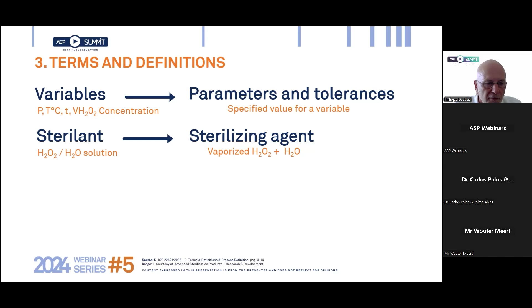Now click again, please. The process challenge device, we'll talk a lot about it in the next slides. It has different meanings according to the sterilization process, but for ISO, it is best explained in paragraph 8.8 of the standard. In essence, 8.8 says that the PCD is a test item that simulates a real medical device. For healthcare facilities, the PCD must be more resistant than the most challenging device. So it's a very important concept. And as I said, we'll come back to that in the rest of the presentation.